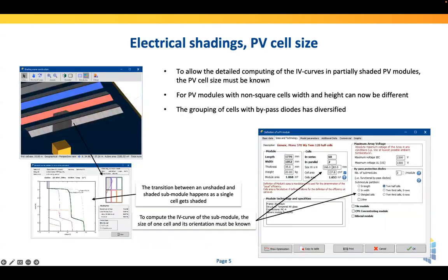Another topic we are working on is electrical shadings. Electrical shadings are the fact that if you partially shade a string or PV module, the current in the entire string or module is impacted, not only the shaded cells. In PVSYST we have a model called the module layout tool, which allows you to calculate the IV curves on a sub-module level — a sub-module being a group of cells protected by a bypass diode. PVSYST calculates the shadings on each group of cells and builds up the complete IV curve, then combines modules into strings and so on.